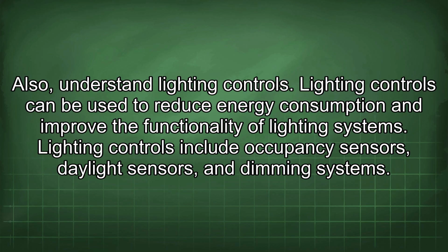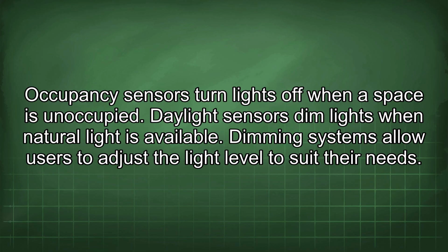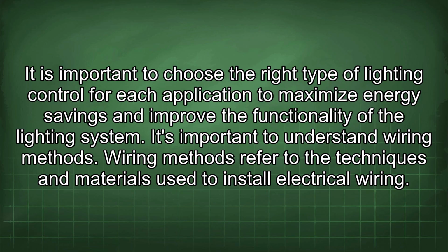Lighting controls can be used to reduce energy consumption and improve the functionality of lighting systems. Lighting controls include occupancy sensors, daylight sensors, and dimming systems. Occupancy sensors turn lights off when a space is unoccupied. Daylight sensors dim lights when natural light is available. Dimming systems allow users to adjust the light level to suit their needs. It is important to choose the right type of lighting control for each application to maximize energy savings and improve the functionality of the lighting system.